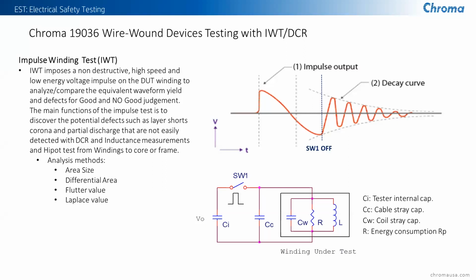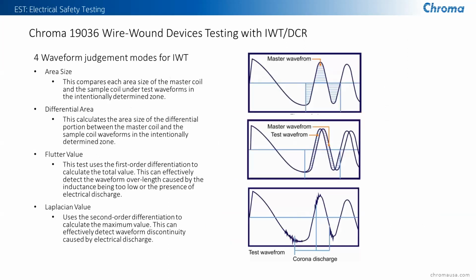But by doing a high-speed measurement of this waveform, we can do a very good analysis to see if there's any alterations that might reflect that there is a difference or an imbalance, or even that there might be a partial discharge occurring between the windings. So there are 4 ways that we do that. There are 4 types of judgments.